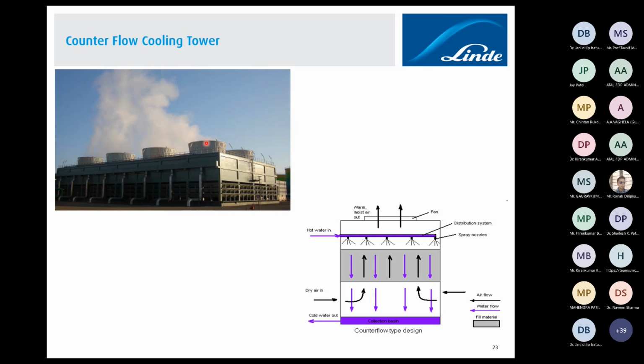And this is how the 8th fan, as a spare, helps us whenever there is a disturbance in humidity, or whenever in monsoon we need to maintain the temperature and because of humidity we are not able to. Sometimes velocity plays an important role. It will not increase drastically, but there is an incremental gain of 1 to 1.5 degrees by running a fan after 2 hours. When you run an additional fan, you will see some improvement in the cold water temperature. This is how it is usually maintained. And in winter, many a time we have to stop 2, 3, and sometimes even 4 fans, depending on the weather condition.